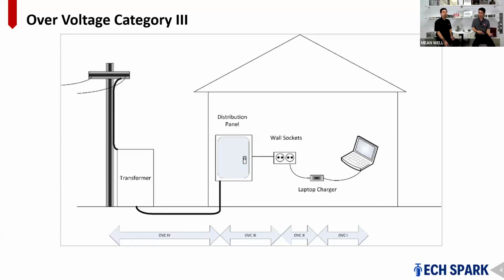Moving to over voltage category 3, it refers to primary fixed equipment fitted inside a switch cabinet or distribution panel, such as relays, circuit breakers, and fixed installation power supplies. Category 4 applies to power utility equipment connected directly to the incoming supply.